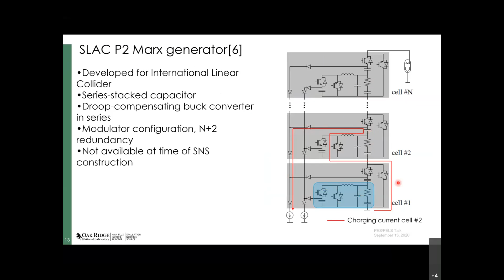Subsequently, a company in Spain called HEMA, when ESS was under consideration to be built in Spain, developed a somewhat similar modulator approach. Here, though, they do not use a buck or boost converter on the output section. They actually use an H-bridge, which feeds the energy storage capacitor after a rectifier section, and then they switch those modules in and out. During the pulse, as it droops, they can play with the phasing of the H-bridge to compensate for that directly, at the low voltage potential. That does offer a lot of advantages.